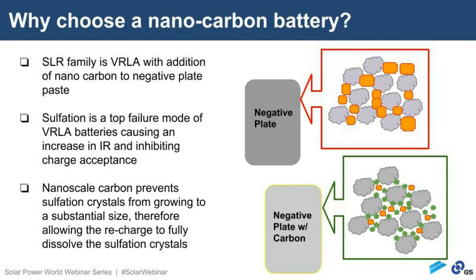I saw another one here, go ahead Richard. I have a question regarding the discharge C rate and charge C rate, I can answer quickly. Maximum discharges are going to be 6C for 5 seconds, 3C for 1 minute, and on our typical 48-volt system we implemented a 250 amp circuit breaker, so that limits the string. For the cell itself, I think the max is around 1C, depending on your string. The charge C rate is always 0.2, so maximum 200 amps. And I think you have pretty good documentation on that too.